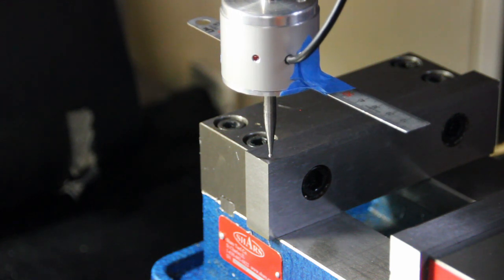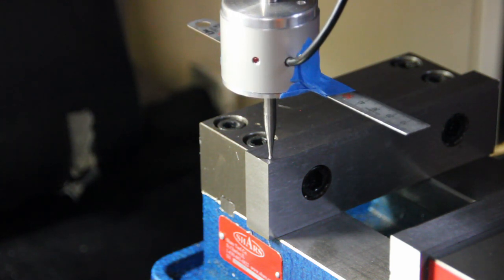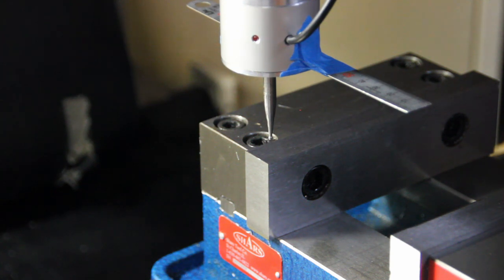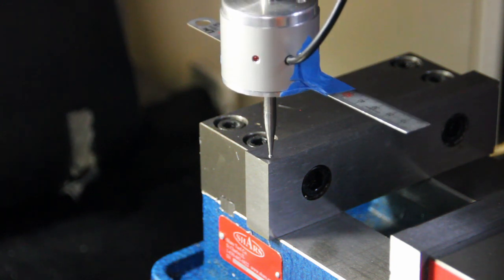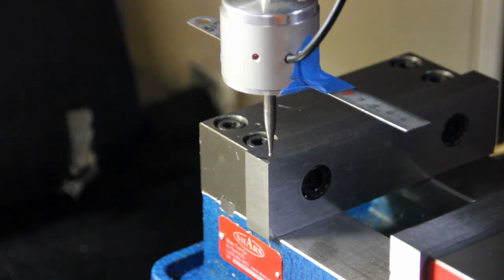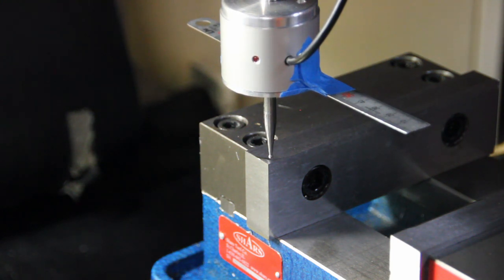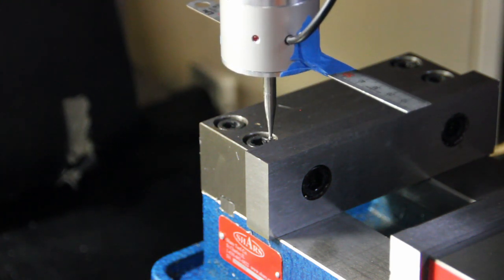Do it 5 times here and see what we get for 5 times. So that's plus 1/10,000th. And minus 1/10,000th. So we're within plus or minus 1/10,000th of 0 for all 5 probes. So that's pretty good repeatability if you ask me. Now that's a straight up and down probe, and that's the repeatability on the straight up and down probe.